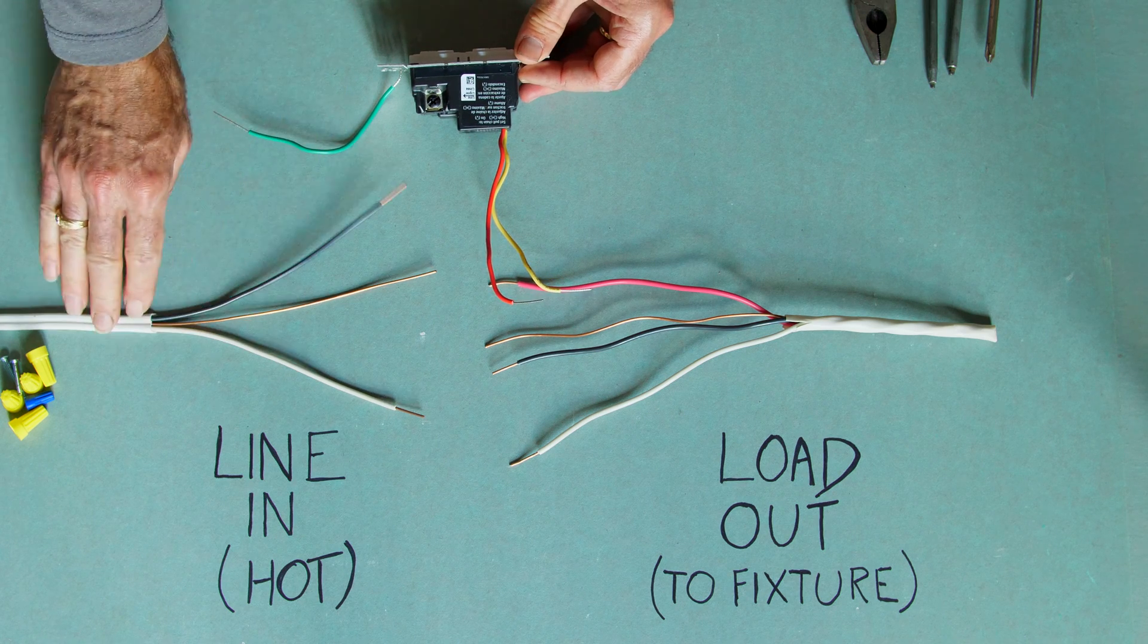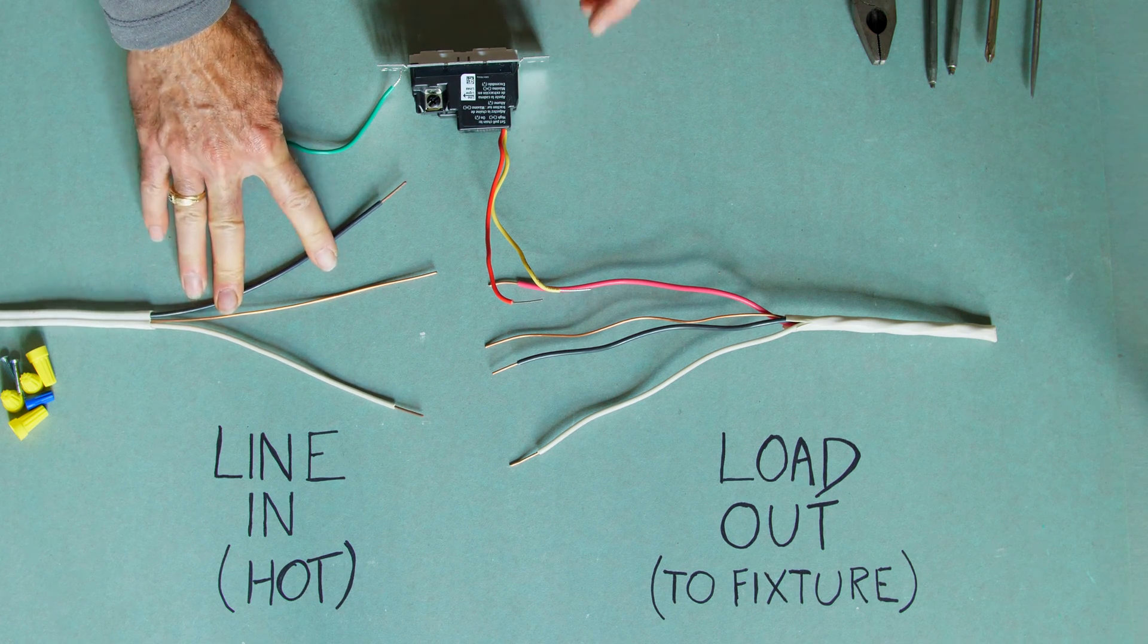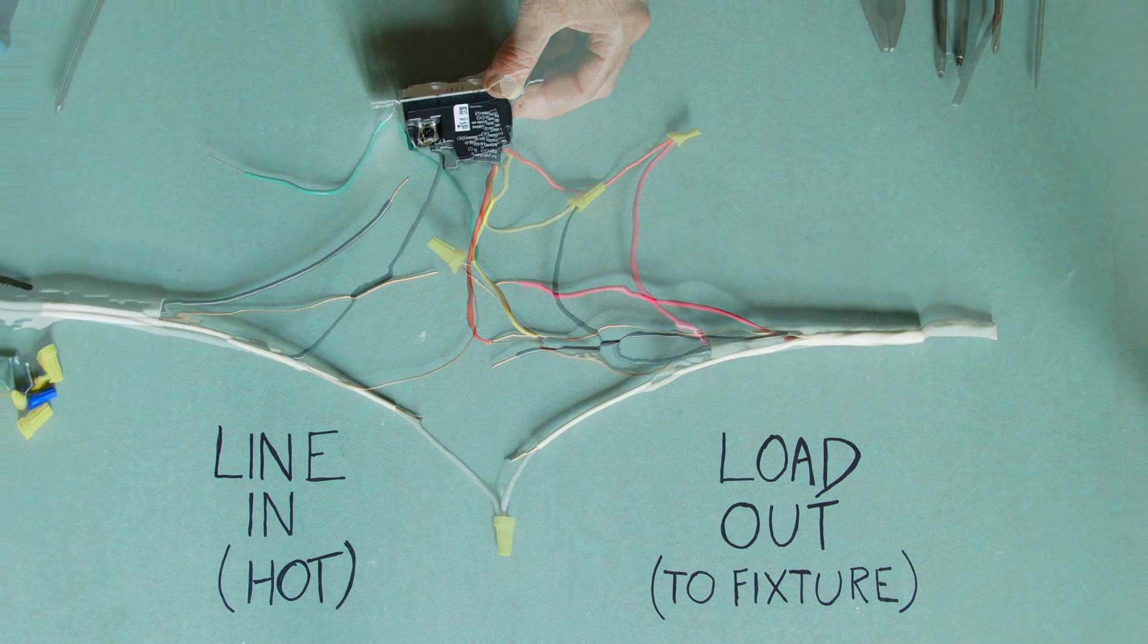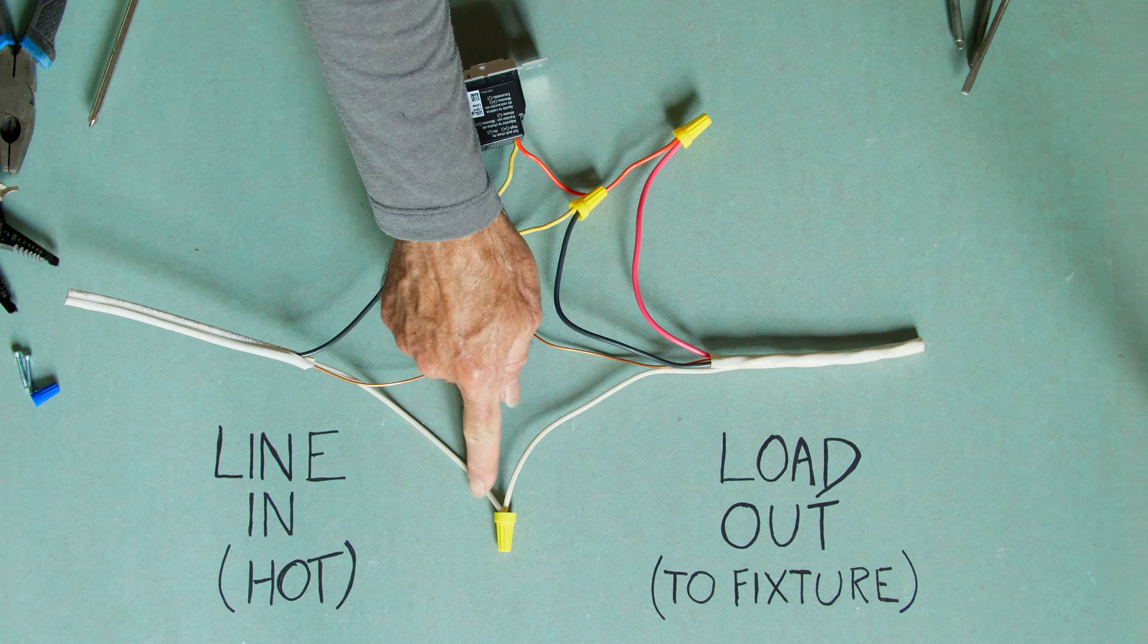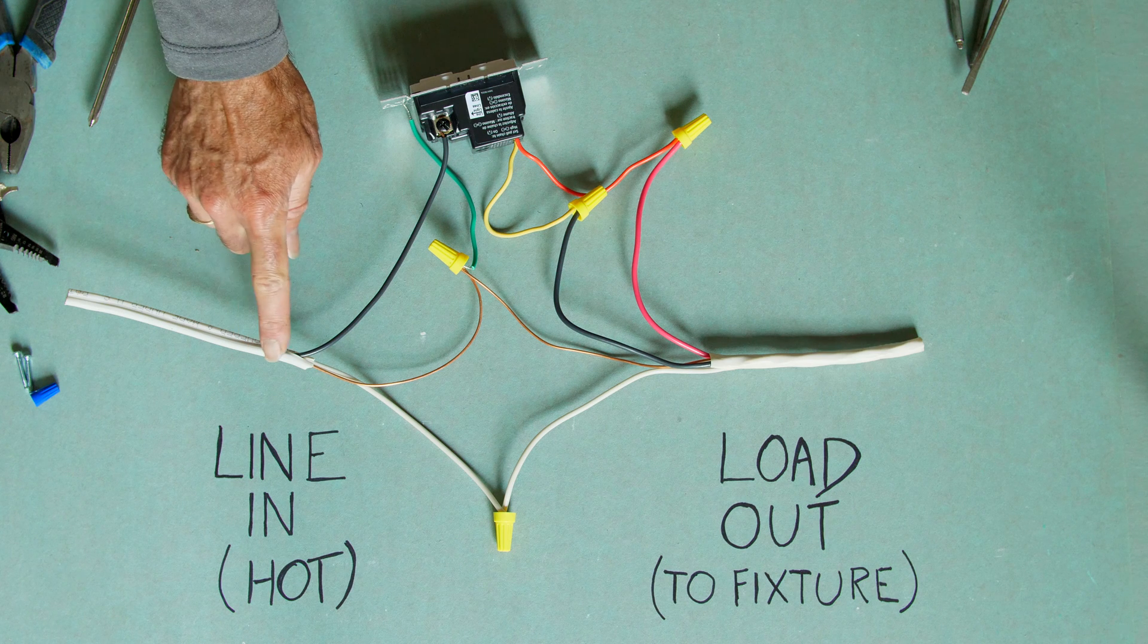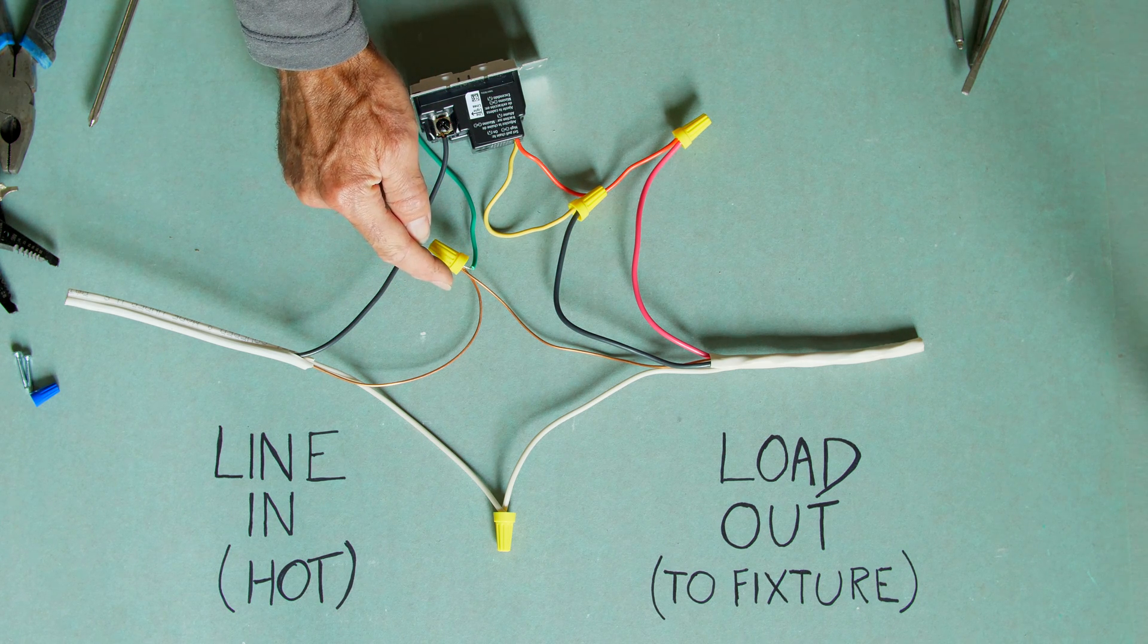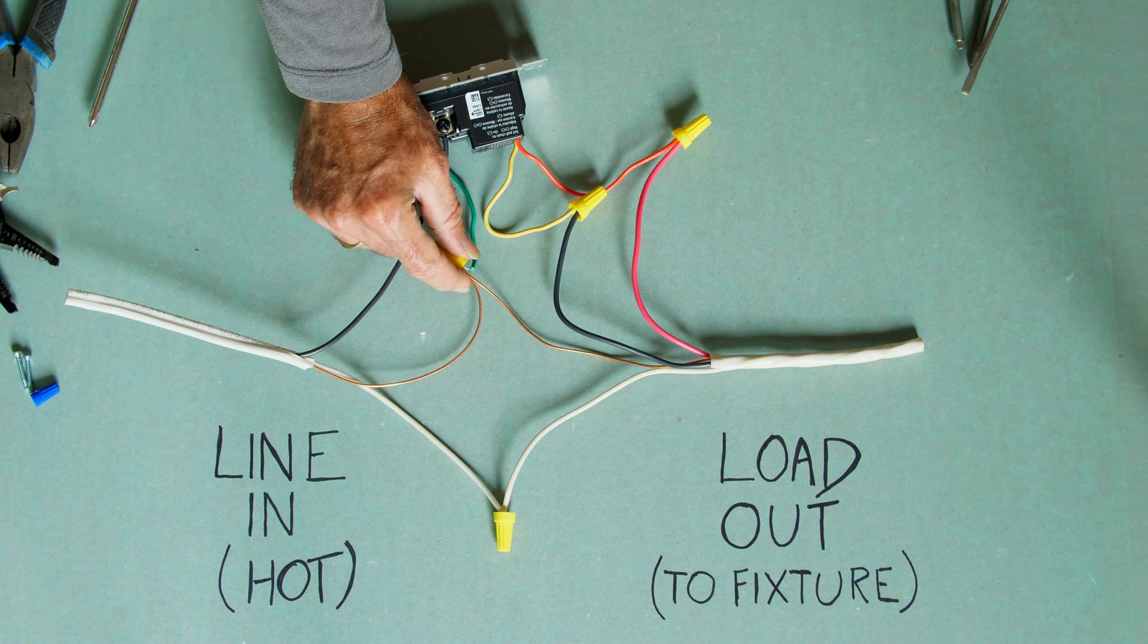So that leaves us just with our black from our line in and this is the hot wire that's giving us our electricity. So that is going to be connected to the screw post on the switch. So when we have all our connections together we can see we've got our white coming from our line in, our power source, to our white of our loadout to our fixture. Our black or hot wire going to the black screw post. We've got all our grounds together and also there should be a ground that's connecting to the electrical box.